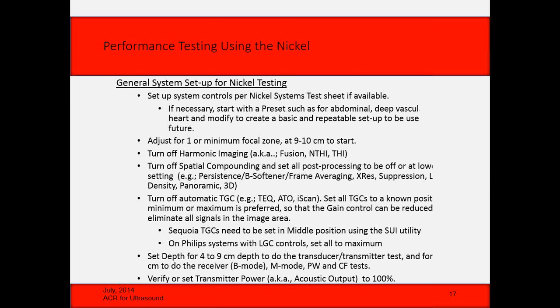Then there's the image uniformity and artifact survey. So using a phantom, the way you do that is get an image on the screen with as much of the phantom as possible, and then adjust the gain upwards so that you start to see a noise level, and then look for streaks, axial or lateral streaks, or dropouts, in other words, which might indicate an artifact. And there's a trick with a phantom of moving it very fast across the top of the phantom. When you move it really fast, if there is a dropout, there's a better chance of seeing it. But frankly, it's very hard to see dropouts unless they're really bad these days, because the transducers are so dense and the systems are doing everything they can to cover up dropout.